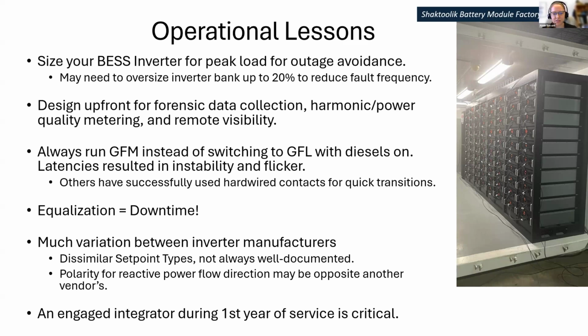We bring this up because UNIFI is focused on the fact that now that we've done a handful of these systems, there's a lot of variation between inverter manufacturers. Some of the set point types that govern synthetic inertia and droop vary a lot from one to the next, and it's not always well documented from an application and user end side of things. So we find ourselves relying pretty heavily on manufacturers to get all of those knobs dialed in on a new system and to tweak them over the first year of service.